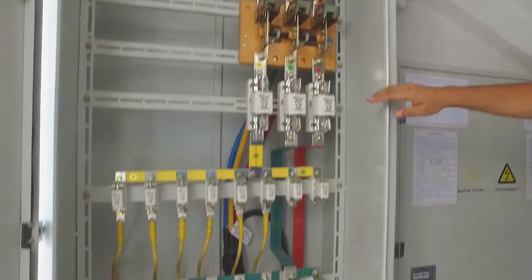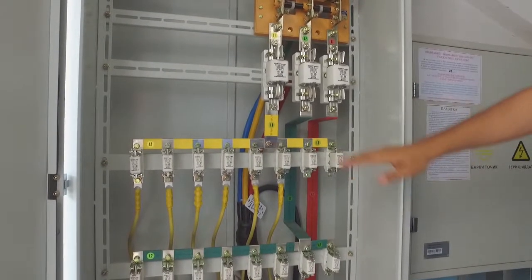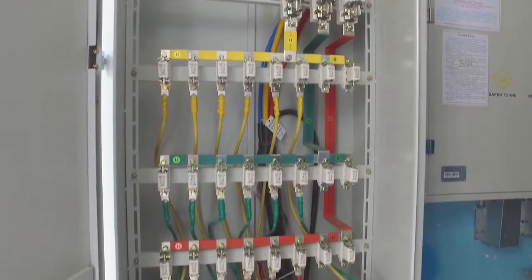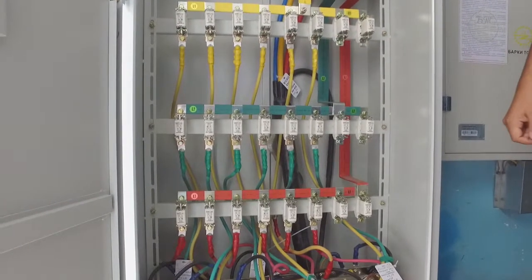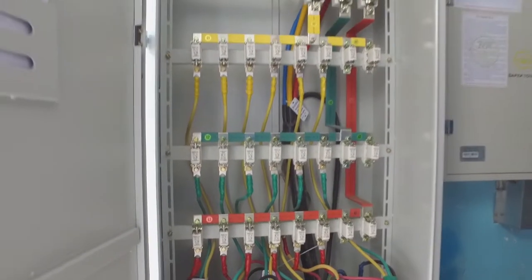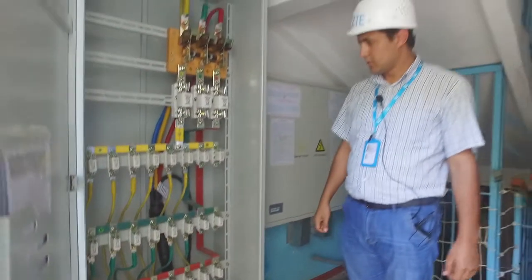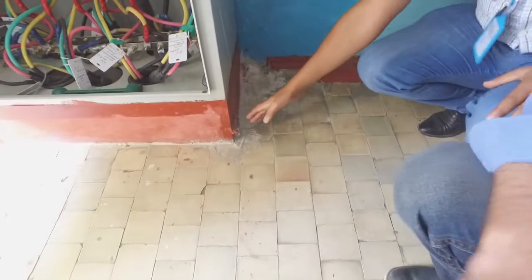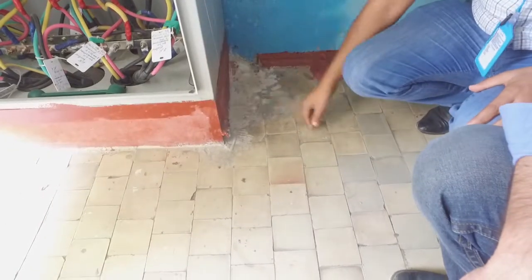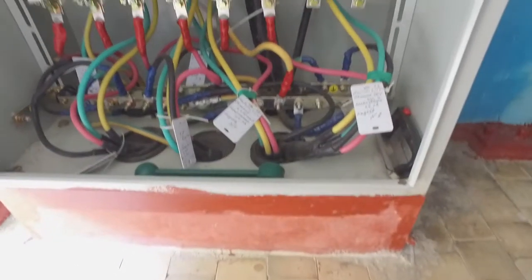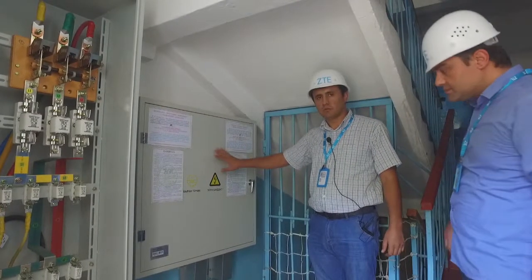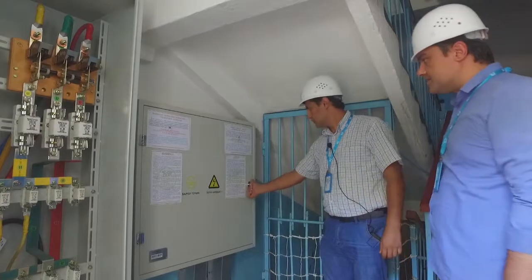Here we can see the set of fuses, 400 ampere, and here are the outgoing lines per phase: phase A, phase B, phase C. Totally we have 8 outgoing lines for 8 different meter boxes. Now 6 of 8 we are using here. Also, this is the grounding bar. From this point we have already grounded our LVDB box, and inside it is connected with a grounding rebar also. Then the cable is coming here to the IMB box. This is IMB 9, an indoor meter box with 9 meters. Let's see inside.